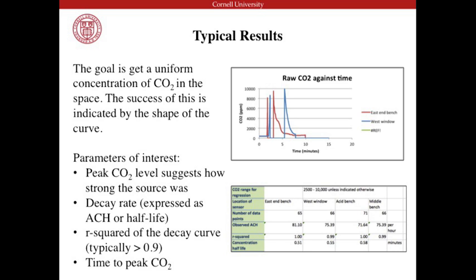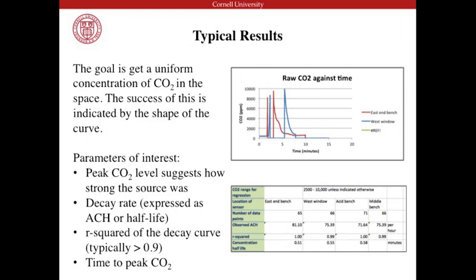We look at the peak CO2 levels. That suggests how strong the source was. Did we actually reach 10,000 ppm? The decay rate is actually the air exchange rate at that location where that meter was. And then we want the R squared value to be above 0.9, because that'll tell us just how good our test was. Anything below that, and we want to redo the test. And then also the amount of time to get up, so the front side of the curve is also important.